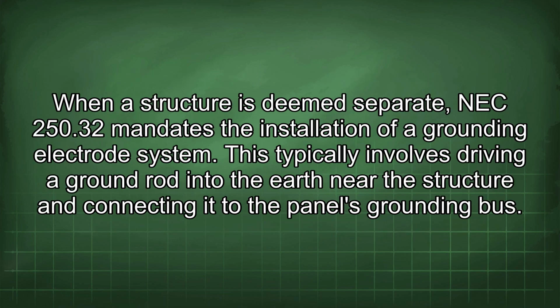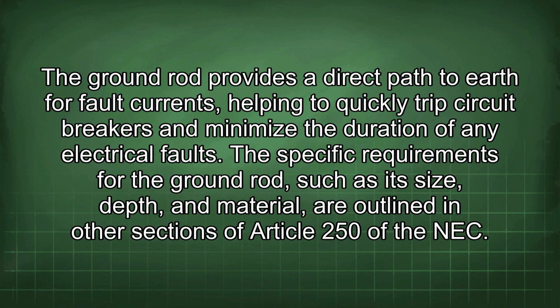When a structure is deemed separate, NEC 250.32 mandates the installation of a grounding electrode system. This typically involves driving a ground rod into the earth near the structure and connecting it to the panel's grounding bus. The ground rod provides a direct path to earth for fault currents, helping to quickly trip circuit breakers and minimize the duration of any electrical faults. The specific requirements for the ground rod, such as its size, depth, and material, are outlined in other sections of Article 250 of the NEC.